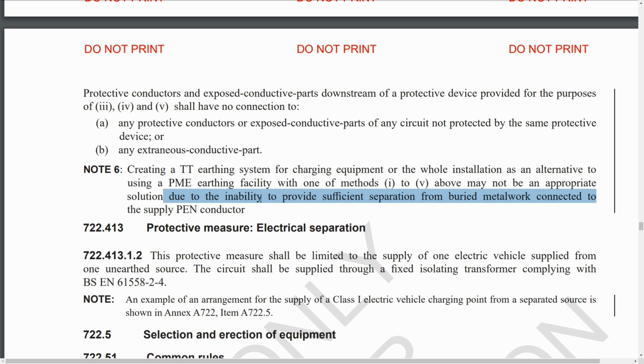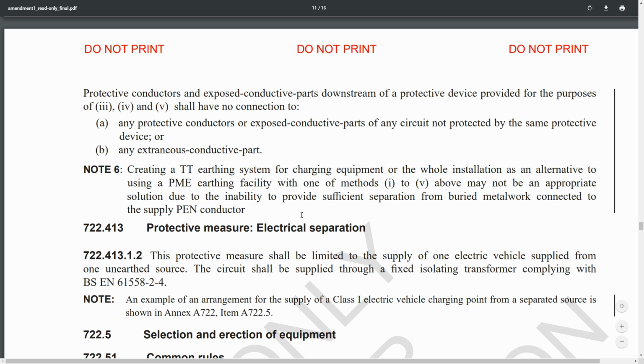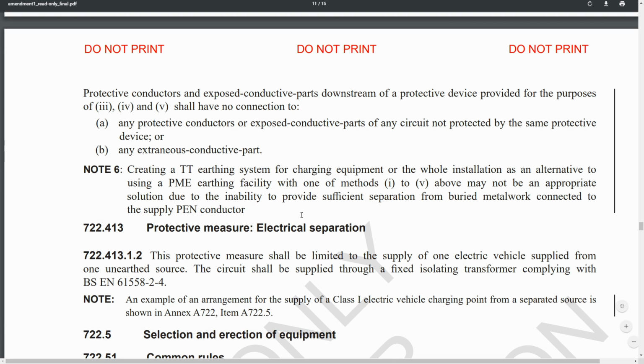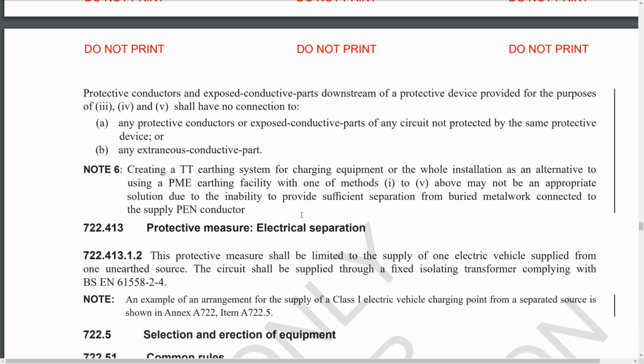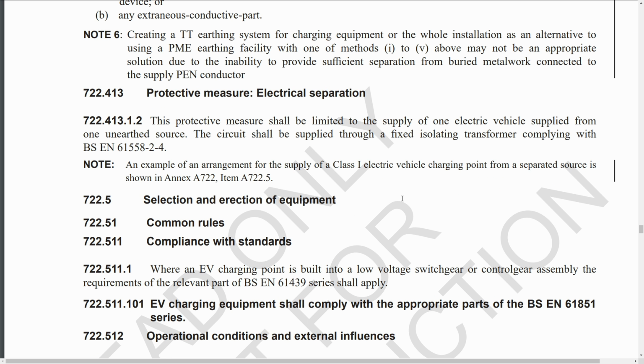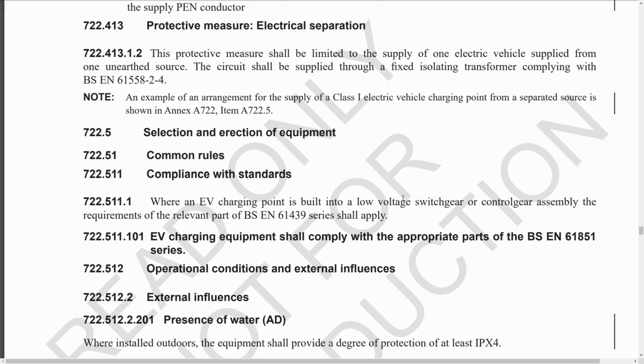You can't put it anywhere near any existing stuff buried underground, and of course that's assuming you even know where things like gas pipes or whatever are buried underground, because that information may not be readily available. So rather than solving a whole load of problems, this really introduces even more. So as previously, just shove in the old electrode and make it TT, not actually such a good idea, because you can't really rely on it being as far away from those other things under the ground as it should be. Now, most of what is here hasn't actually changed particularly.